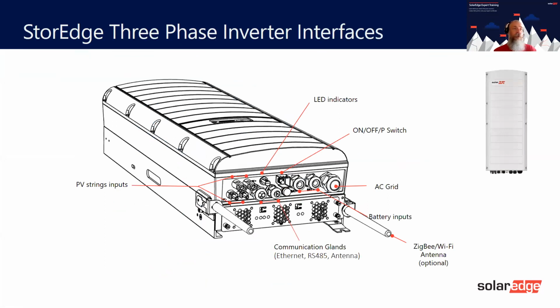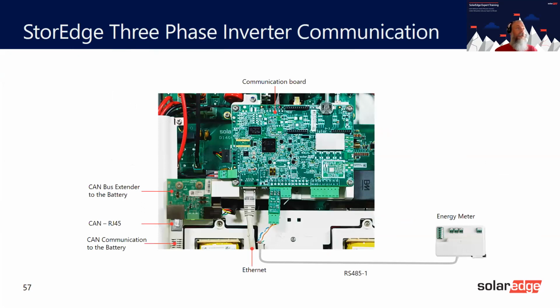This is the bottom of the inverter. It looks slightly different because the battery plus and minus are taken in here. The AC is the same, the MC4 is the same, communications are the same, but these 2 here are where the battery cables enter. And this communication board you've already seen. You can see we've got the RS485 going in here, Ethernet into here, and this bit here is the battery communication, the CAN bus. And that all plugs in together.